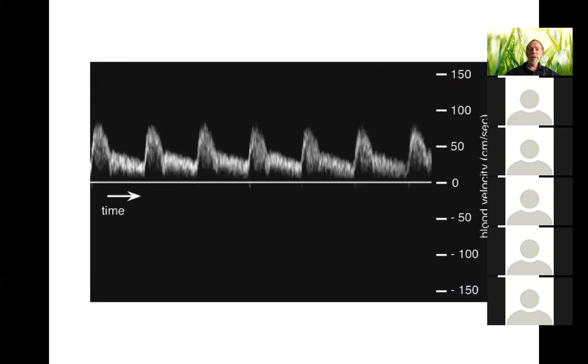Here's what it displays externally. It's the same display, but with one important difference. It's calculated velocity values from the Doppler shift values. The display is still the same, but now we can read off the velocity values. As I've mentioned several times, to do this, it must know the Doppler angle. Otherwise, these values are meaningless.